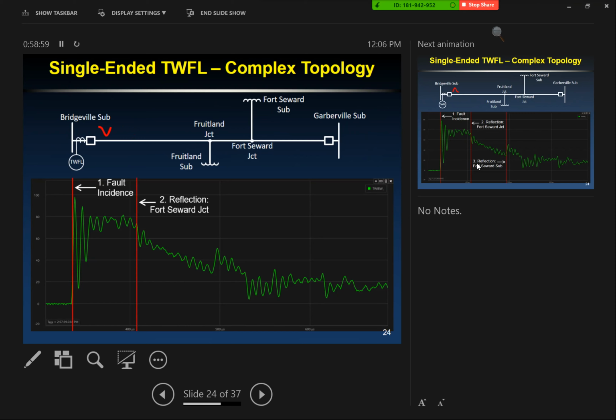Now what happened is it wasn't exactly an inversion. As the traveling wave is propagating down the tap, the current flow is into the fault. When it goes toward the right - I'll rewind and show it again - the traveling wave is flowing to the right, but which way is the current flowing? Back to the fault. So that's shown as a negative polarity because I want to keep everything consistent. Our relays are looking to the right, so everything to the right is positive from that relay's perspective. You have to keep everything in reference to right is positive.